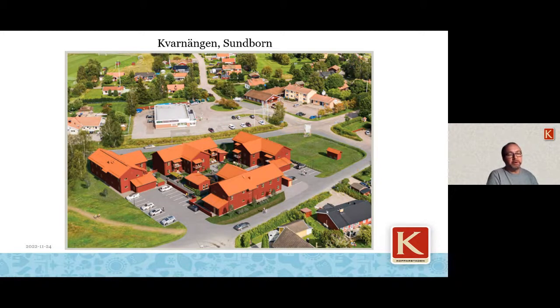Half of the apartments we had earlier had direct electrical heating, and the rest had used a heat pump for heat and hot water. On really cold days, an oil boiler was also started when the heat pump didn't manage to keep the temperature up. The heat pump in the old buildings had been in use since 1995 and was functioning worse and worse. When we started building the 24 apartments in the red houses in front in 2019, it was necessary to take a new holistic approach for heating existing and new buildings.